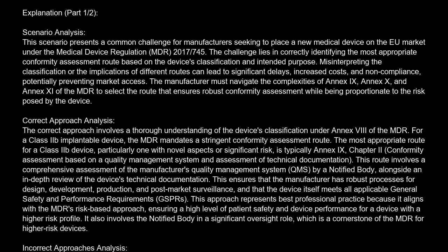This ensures that the manufacturer has robust processes for design, development, production, and post-market surveillance, and that the device itself meets all applicable general safety and performance requirements, GSPR. This approach represents best professional practice because it aligns with the MDR's risk-based approach, ensuring a high level of patient safety and device performance for a device with a higher risk profile. It also involves the notified body in a significant oversight role, which is a cornerstone of the MDR for high-risk devices.